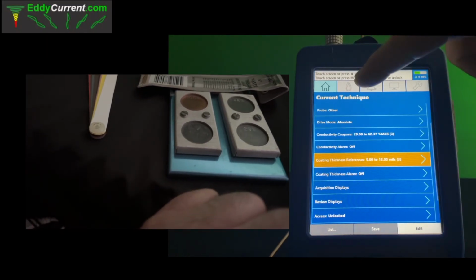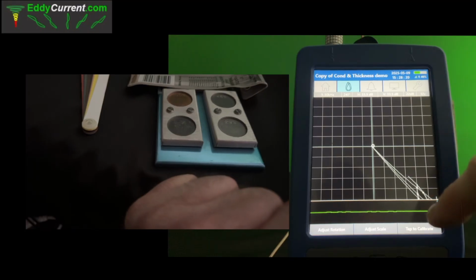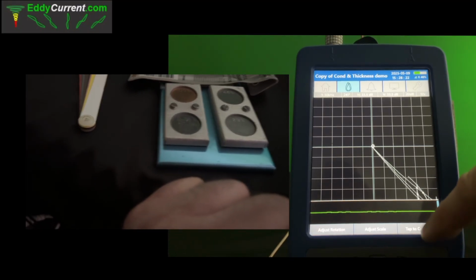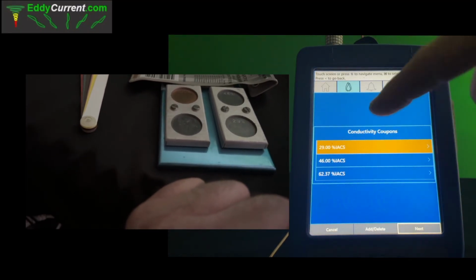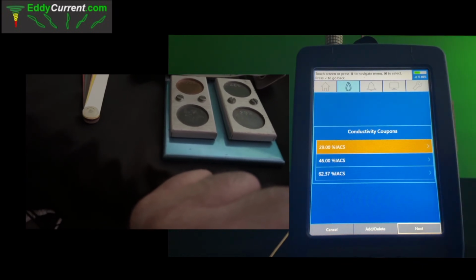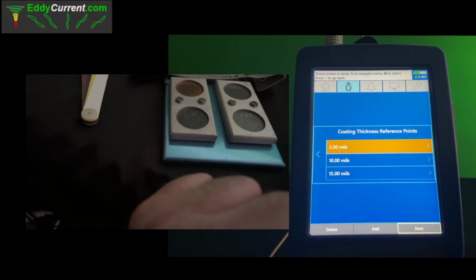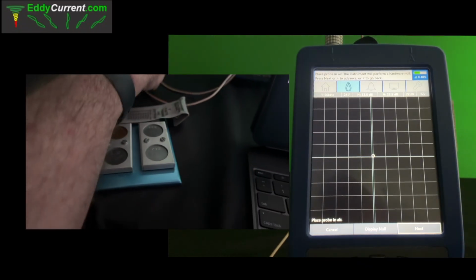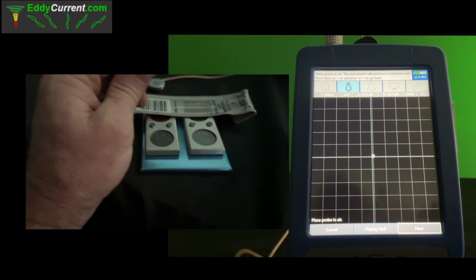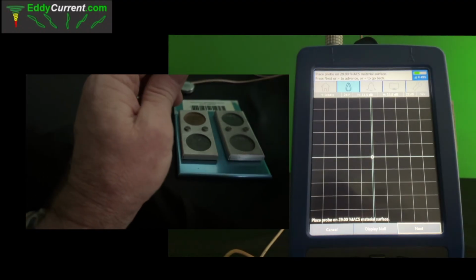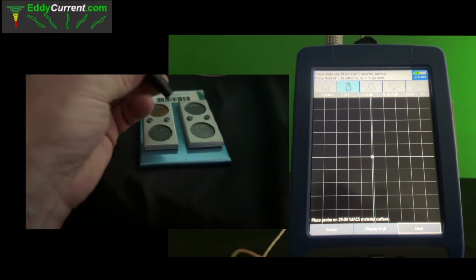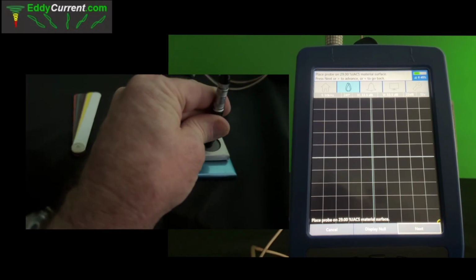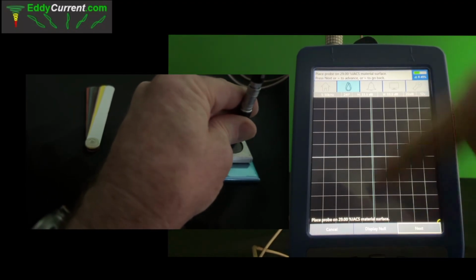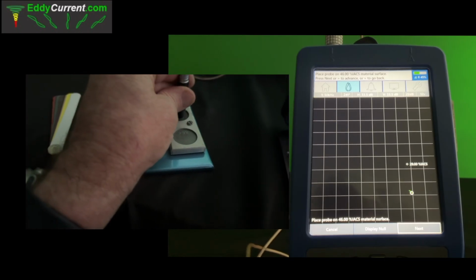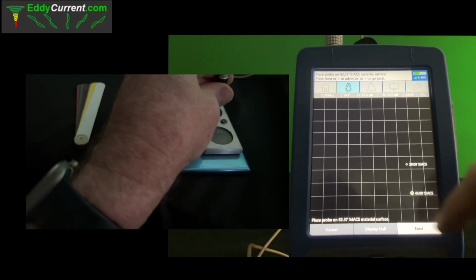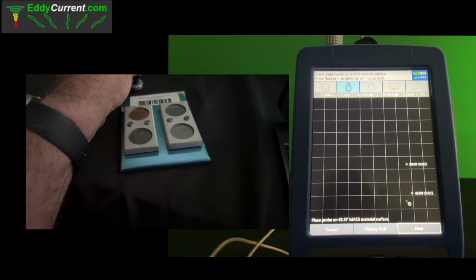And then I'm going to click on this little caliper, which brings us into the calibration menu, and click tap to calibrate. It's just going to have me verify my values, so those look good. My shim values look good. So now it's just going to have me hold my probe in air and click next. Then it's saying place your probe on the 29% IACS, which is this one. Then we're going to do the 46. And finally, the 62.37.